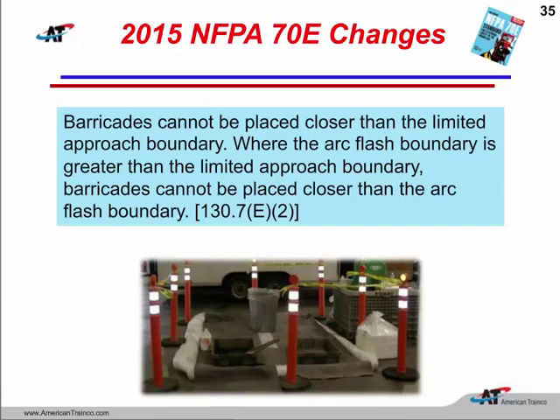Barricades, very, very important. The barricades cannot be placed closer than the limited approach boundary, but if the arc flash boundary is greater than that limited approach boundary, then the barricade cannot be placed closer than that. So remember that the limited approach boundary is a shock protection boundary. They're trying to protect that qualified electrical worker from shock. The arc flash boundary, we are trying to protect that electrical worker from heat. So that's a boundary that would either come off the tables that we see inside 70E if we're going to use the arc flash PPE category method, or it's going to be a boundary that is generated from the software if we do the analysis method.